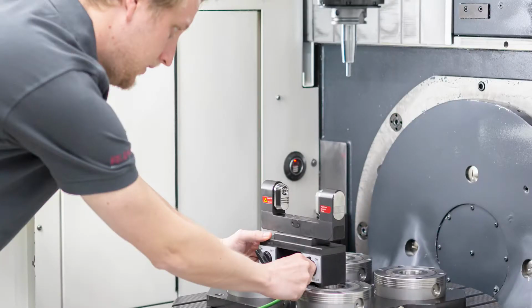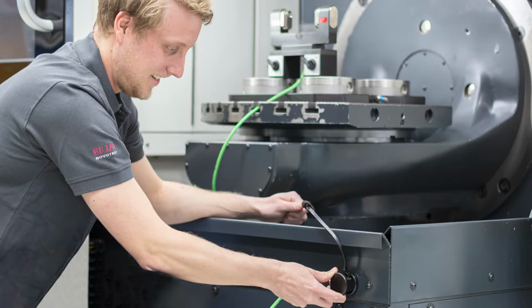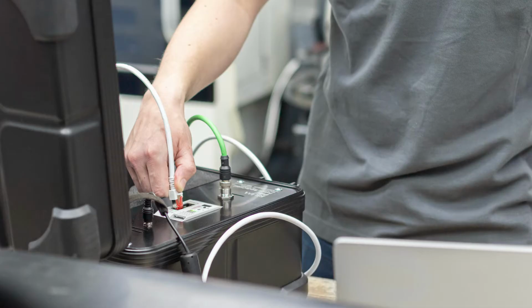With this adaptable solution, the laser is positioned on the machine table using the magnets, then the LC50 Digilog is connected to the interface in the case and the laptop using the connection and ribbon cables. The advantages of this adaptable solution are the versatile evaluation options, which reflect the spindle and thus the machine status.